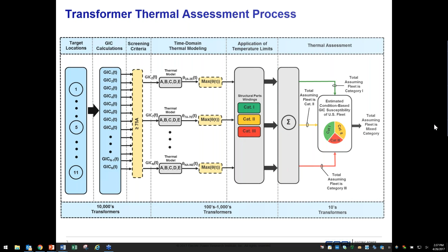And while it's a complex slide, I apologize for the complexity, we have basically summarized all of the process here. We ran every transformer, all 37,000, as category 1 transformers, saying if they were all in good condition, what would the failures be based off a single blast. Then we ran all category 2s, we ran all category 3s, and then we moved the blast around. So we did this 11 different times, and we came up with a number of failures, and then we applied a statistically valid sampling of the condition of the U.S. fleet. For example, a large percentage of transformers fall into category 3. In fact, category 3 is the largest percentage. So we made the assumption that if our 1,400 transformer database is 50% category 3, then we applied that to all 37,000 transformers.